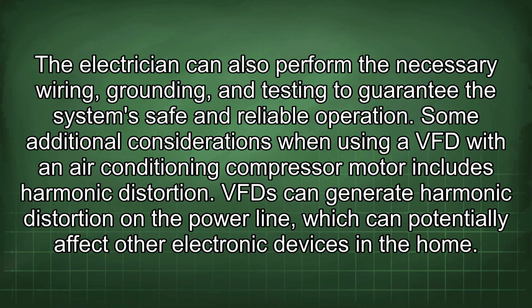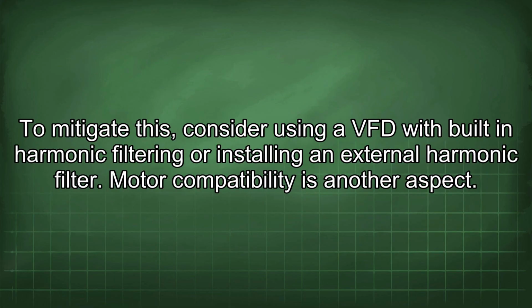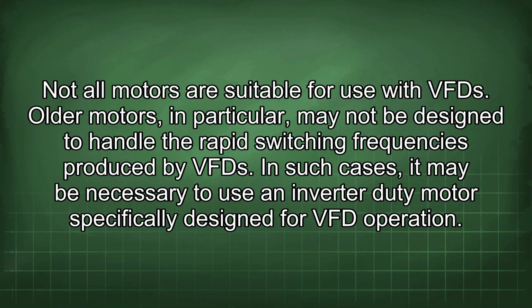Some additional considerations when using a VFD with an air conditioning compressor motor include harmonic distortion. VFDs can generate harmonic distortion on the power line, which can potentially affect other electronic devices in the home. To mitigate this, consider using a VFD with built-in harmonic filtering or installing an external harmonic filter. Motor compatibility is another aspect. Not all motors are suitable for use with VFDs. Older motors, in particular, may not be designed to handle the rapid switching frequencies produced by VFDs. In such cases, it may be necessary to use an inverter duty motor specifically designed for VFD operation.